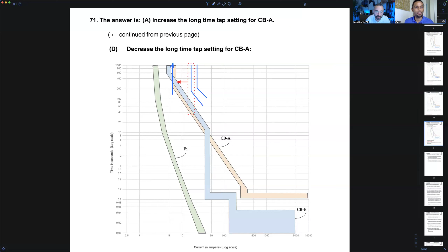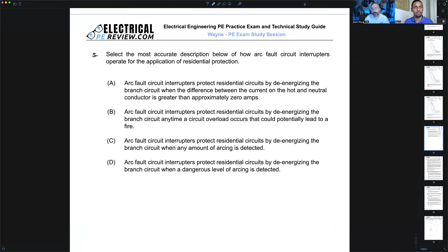It's really just like a puzzle - how do I get everything so there's no overlap, no miscoordination generally. Coordination means I want the minimum number of breakers to open so my outage is as small as possible. When there's miscoordination, more than one device opens and you get a much bigger, widespread outage.